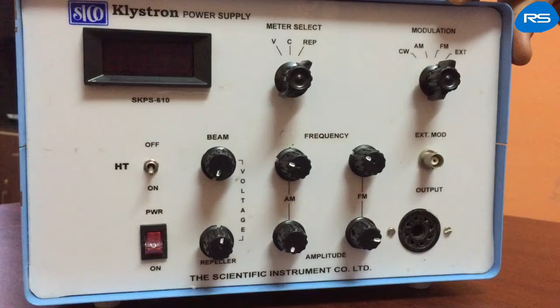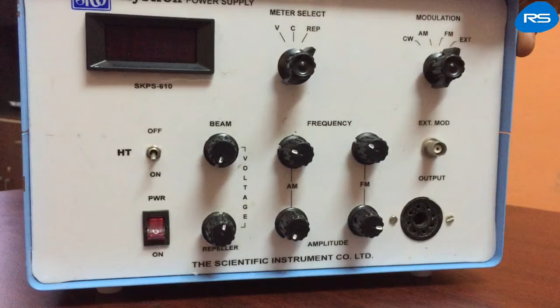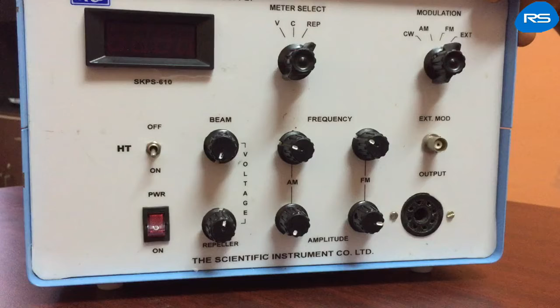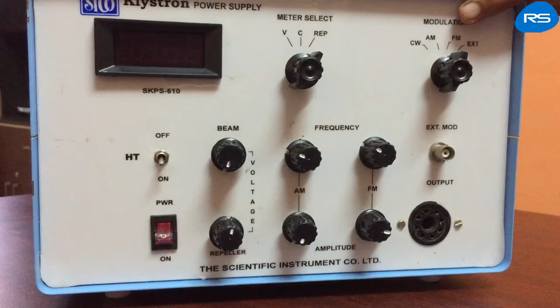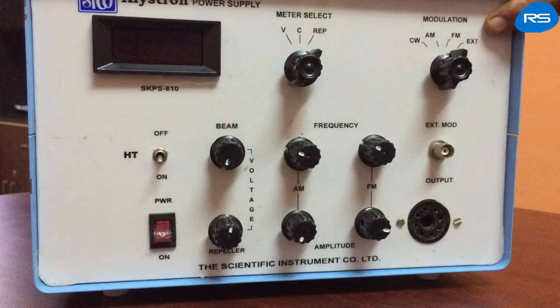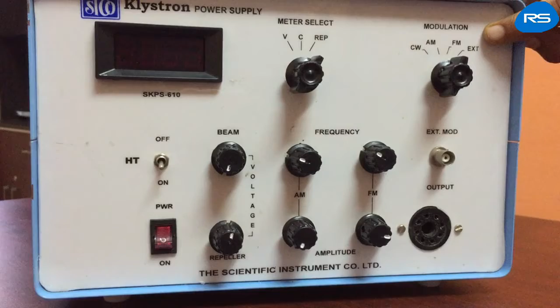Amplitude modulation can be applied with 0 to 110 volt peak to peak square wave and with frequency of 500 Hz to 2.5 kHz. This amplitude modulation is generally used along with VSWR measurements in the slotted line carrier technique. Frequency modulation is used for direct display of Klystron modes on the oscilloscope. Carrier wave operation and external modulation facilities are also provided with the instrument for generalized use.